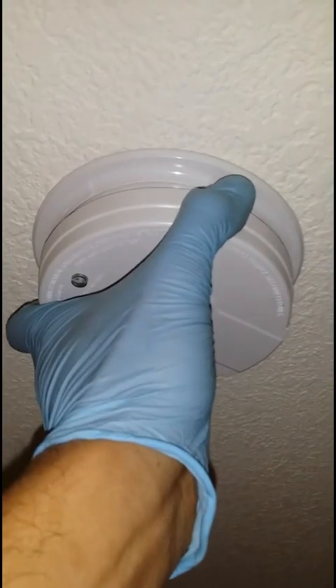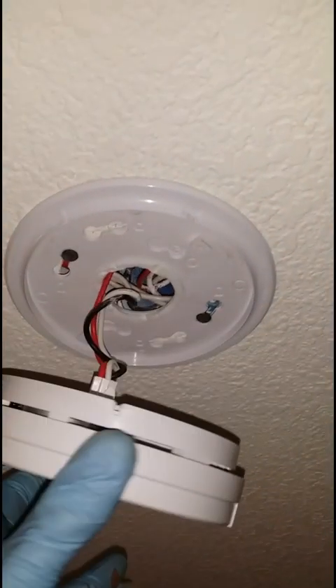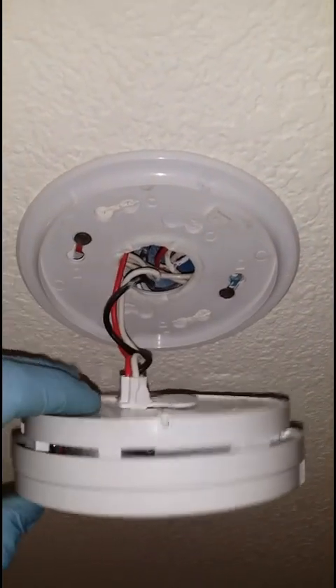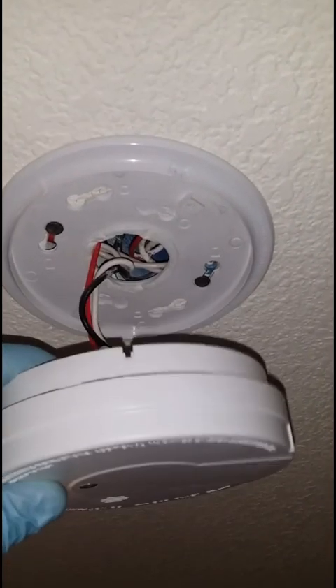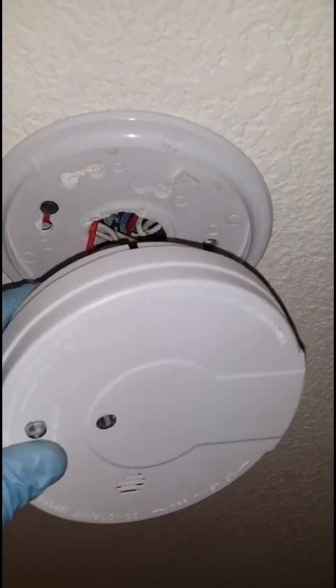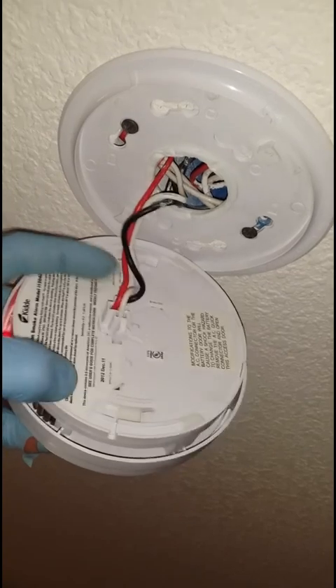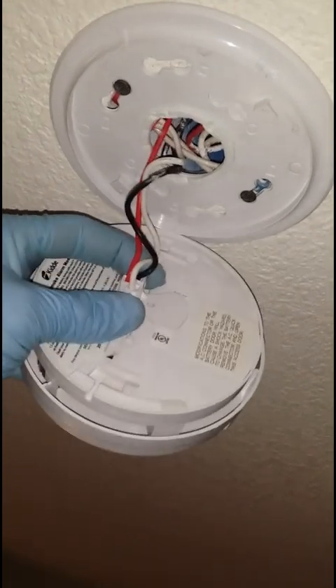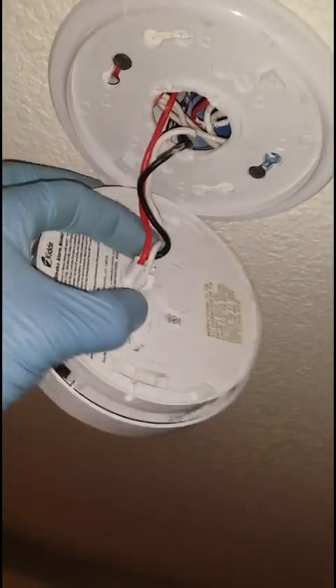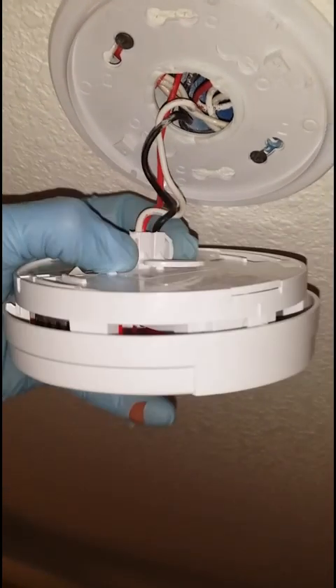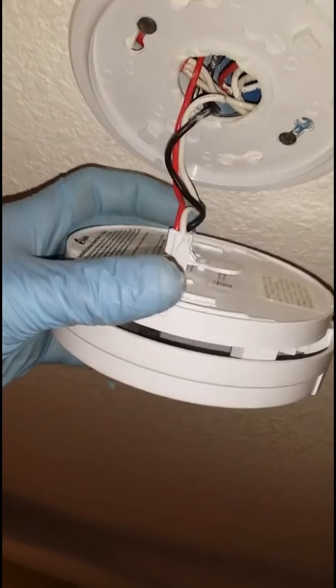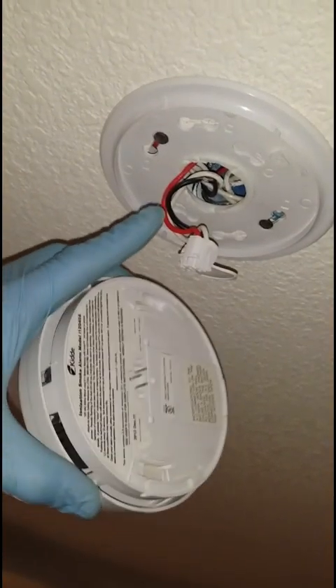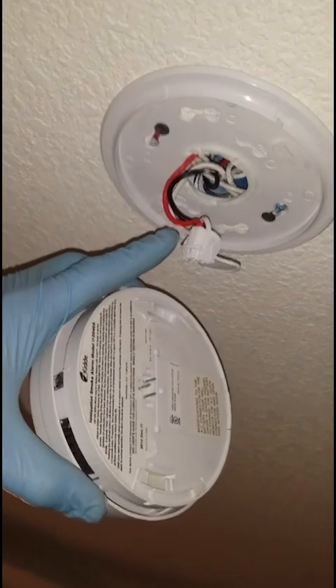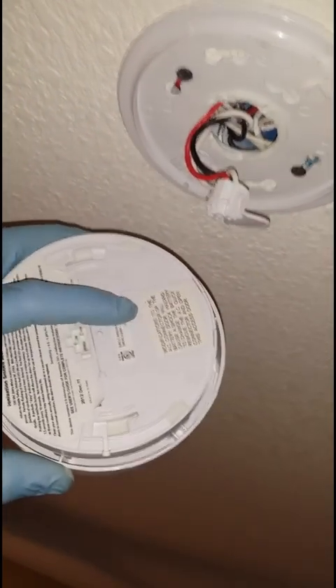Remove the smoke detector from its base. Every smoke detector is different. You may have different ways to remove it from the base, but this is pretty much standard. Once you remove it from the base, you're going to want to take these wires and remove these wires. There's two little push pins on the side. All you basically do is squeeze it and then you pull these wires and separate the smoke detector from the line voltage. Now you can see here the line voltage is going to be 120 volts, and then you have here the batteries in the back.